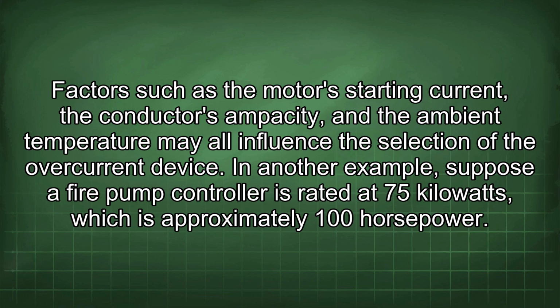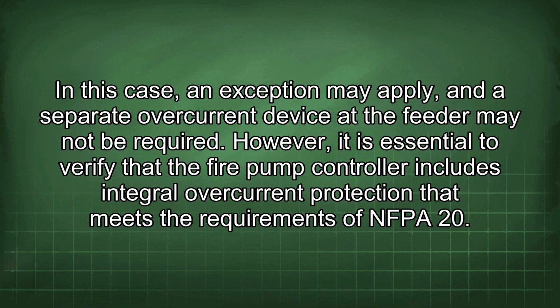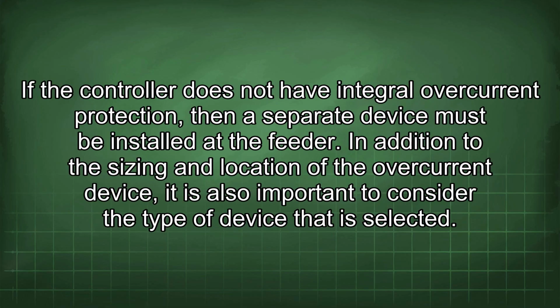In another example, suppose the fire pump controller is rated at 75 kilowatts, which is approximately 100 horsepower. In this case, an exception may apply, and a separate overcurrent device at the feeder may not be required. However, it is essential to verify that the fire pump controller includes integral overcurrent protection that meets the requirements of NFPA 20. If the controller does not have integral overcurrent protection, then a separate device must be installed at the feeder.